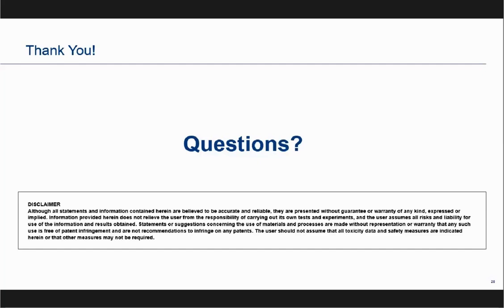We got a question about adiabatic pads, evaporative pads, to reduce condensing. We haven't tested the unit with aftermarket evaporative pads. I know that those are starting to become popular in some desert environments, hot, dry environments. I don't know that we've tested those on any outdoor condensing units really. But if you have an application and you're interested in trying that, again, it probably would be best if you consulted with your application engineer and talked to them about what you want to do and why you want to do it. I don't see any reason why that wouldn't work.